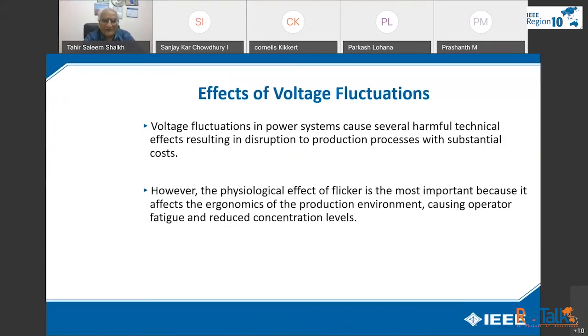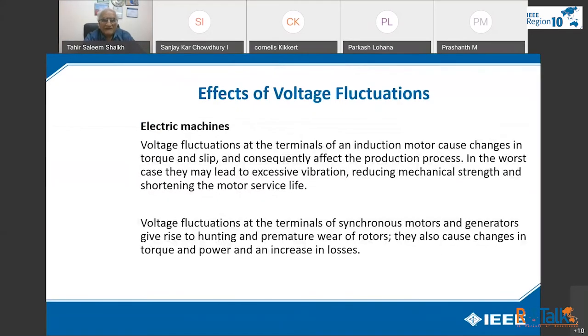Voltage fluctuations in power systems cause several harmful technical effects, resulting in disruption to the production process with substantial cost. However, the physiological effect of flicker is the most important because it affects the ergonomics of the production environment, causing operator fatigue and reduced concentration levels. In electric machines, voltage fluctuation at the terminals of an induction motor causes changes in torque. The torque will vary, and there will be a humming sound and changes in slip, and consequently it affects the production process. In the worst case, it may lead to excessive vibration, reducing mechanical strength and shortening the motor service life. Voltage fluctuation at the terminals of synchronous motors and generators gives rise to hunting and premature wear of rotors. It also causes changes in the torque and power and an increase in losses.